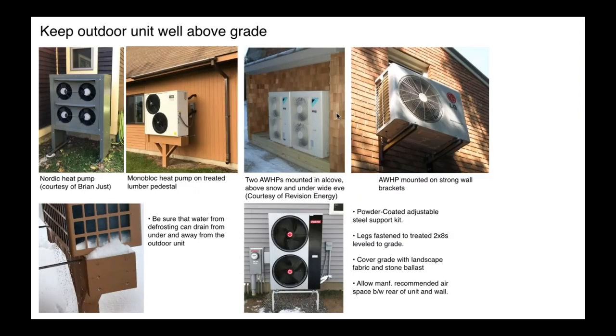Okay, we've got a few minutes left. I'll run you through some details. It's important, especially in northern climates, to get that condenser unit, that outdoor unit, up off the ground. Whether you do it like this, in this case, they put in 6-inch diameter sonotubes, filled them up with concrete, and they bolted that down. Certainly, if you're in an area that has high wind speeds, you don't want this thing bouncing around outside when you get a storm coming through.